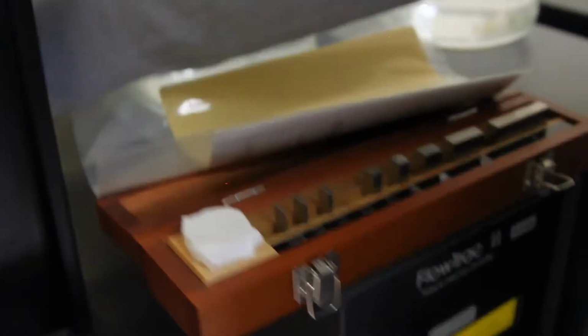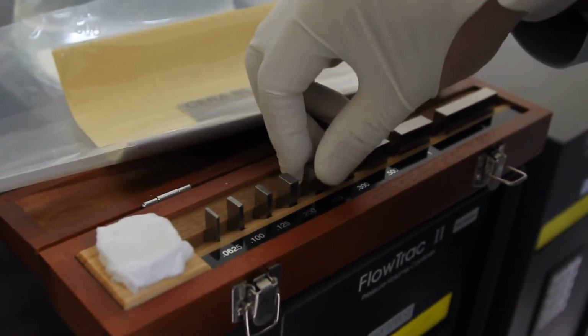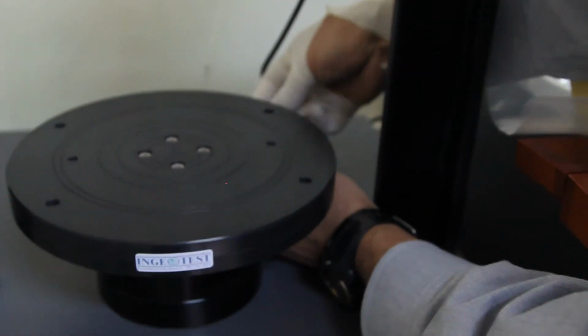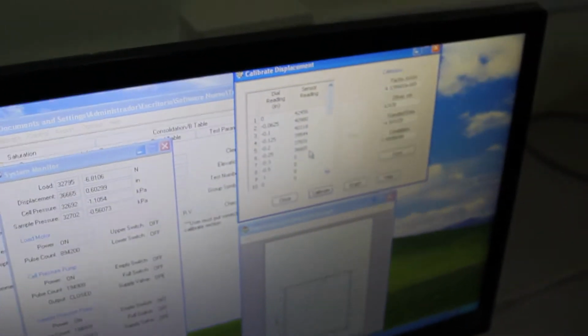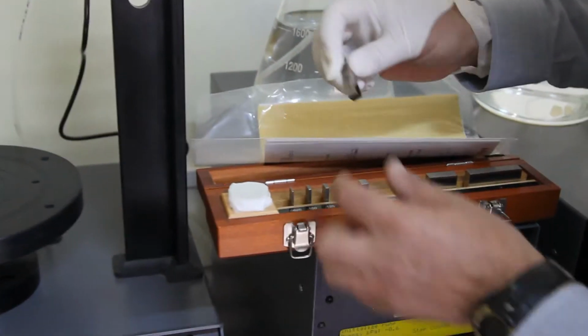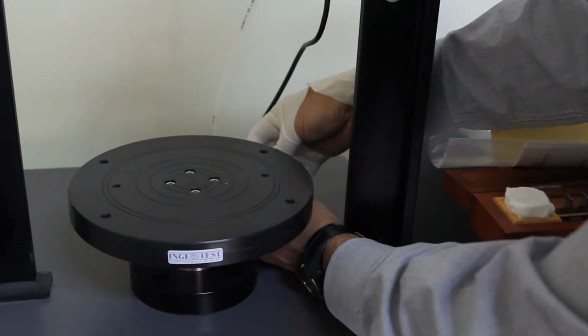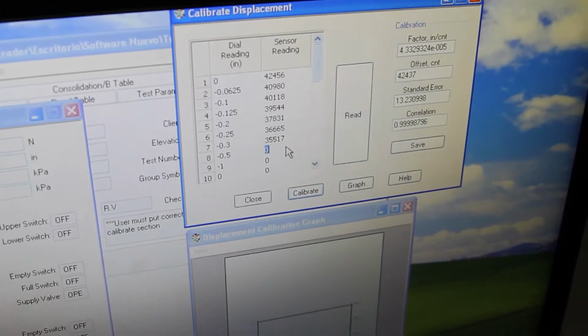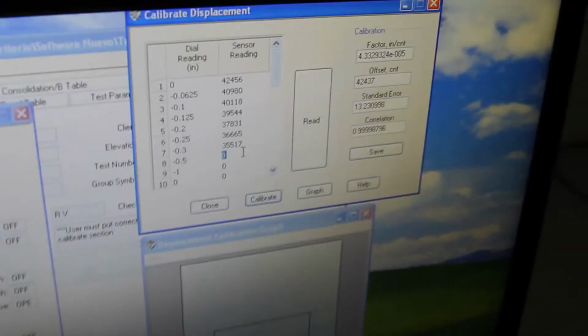So my calibration is taking place. I am already on the fourth point. So my next one. While I'm doing this calibration, I want to make sure that there is no bad point or that something is not right, and I can tell in the graph if a point is completely off or the error is too big on each point. What you see here, so we have my next point, and while I'm keeping track, my correlation has to be at least 4 nines and my standard error as low as possible.